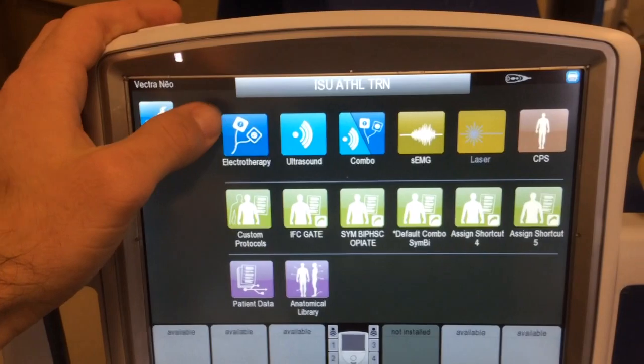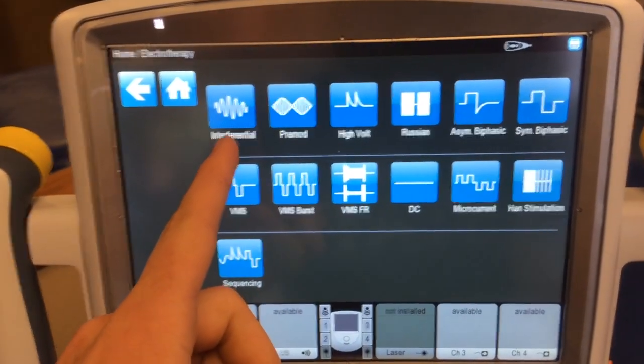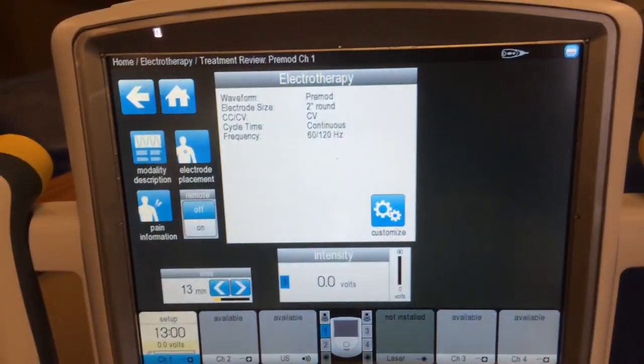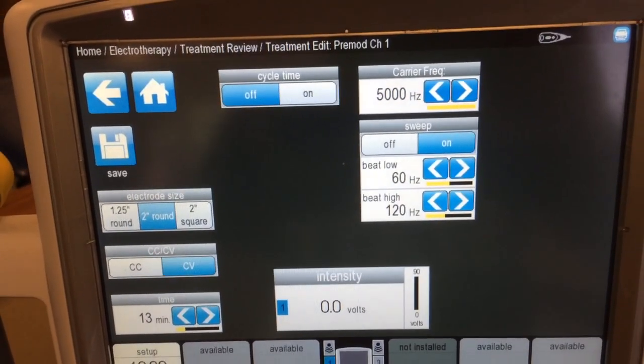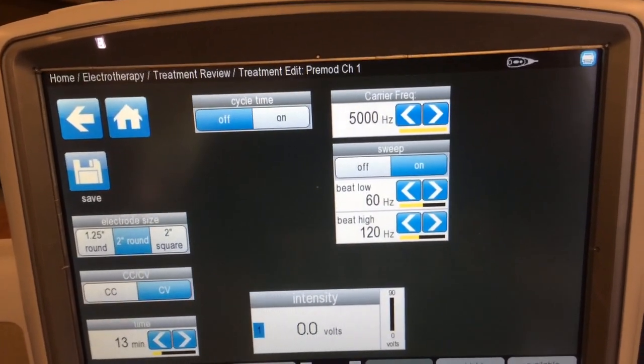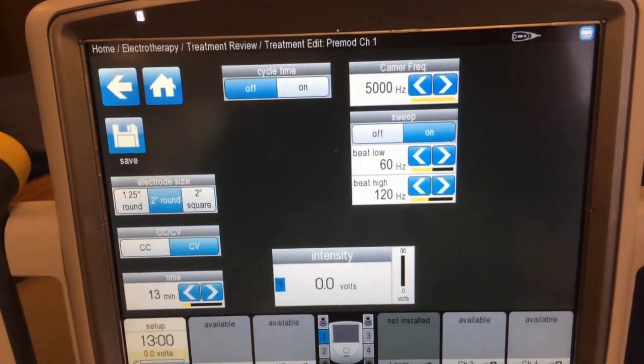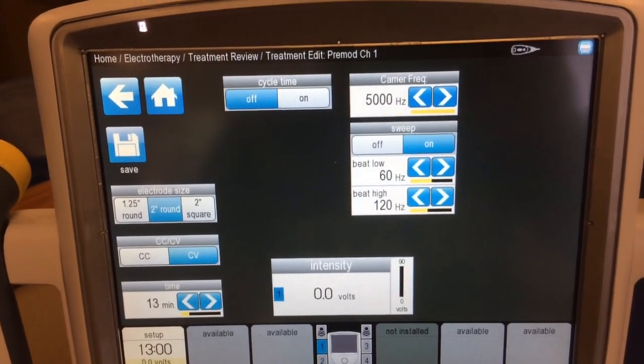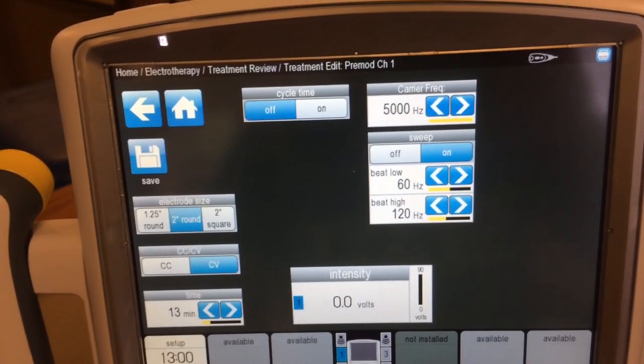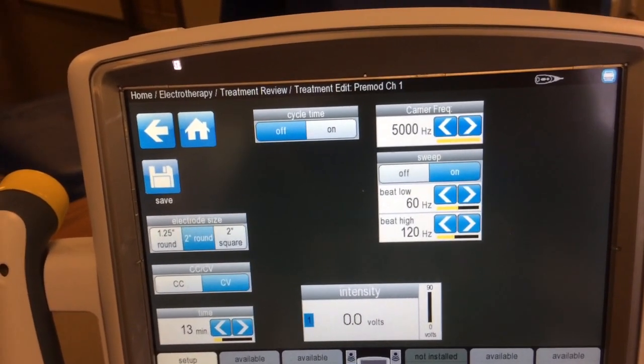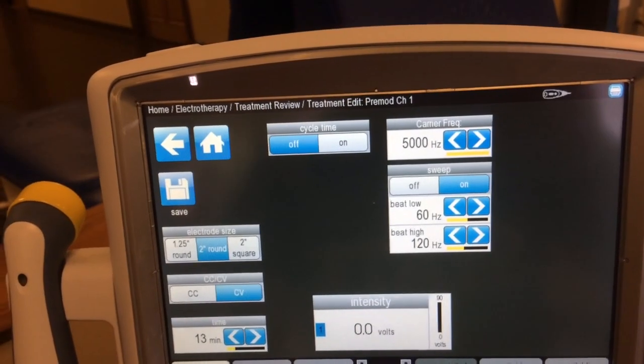Pre-mod is essentially the same concept as Interferential except everything is already pre-modulated and set for you. The frequency is already set at 60 to 120, the carrier frequency at 5,000, which allows a wider span or sweep. You aren't able to adjust any other parameters since everything is preset. It's a simple setup for level one pain control, since we can't change the phase duration.